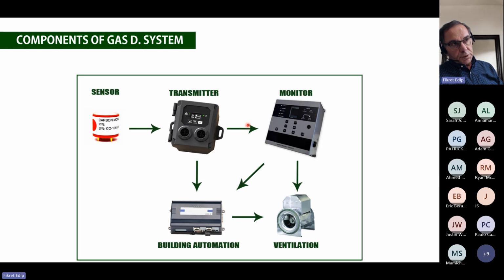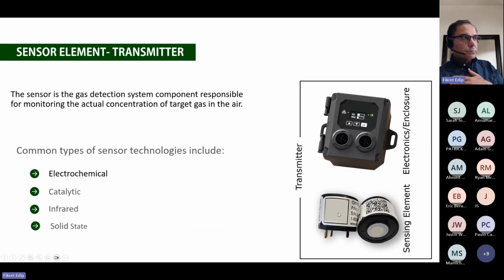In some cases, you don't need this if your building automation system is doing the job of ventilation control. So you eliminate the controller. Instead, the signal goes directly to the building automation system. The building automation system, or BAS, takes care of it. The sensor element is very important. There are 4 types in general that we use: electrochemical sensors, catalytic sensors, infrared sensors, and solid state sensors.